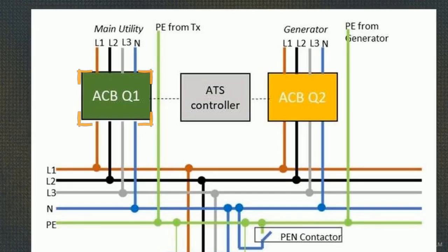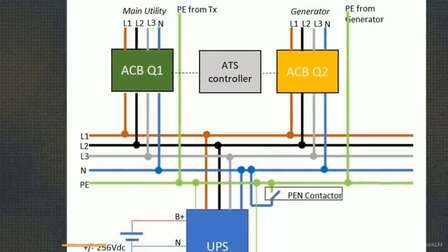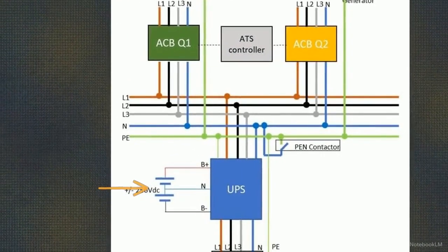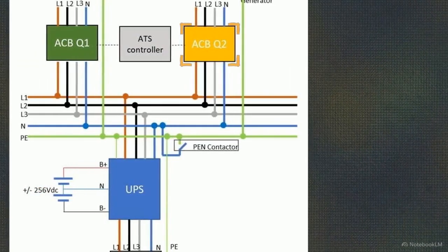Because this is a manual operation, the transfer does not execute automatically. You must physically start the standby generator and monitor the panel to verify source 2 has reached acceptable voltage and frequency limits. Once the generator is ready, you press execute. Breaker Q1 snaps open, and the UPS batteries take the critical load. The ATS validates the generator supply. With source 2 confirmed healthy, Q2 closes to lock in the generator feed, and battery discharge halts.